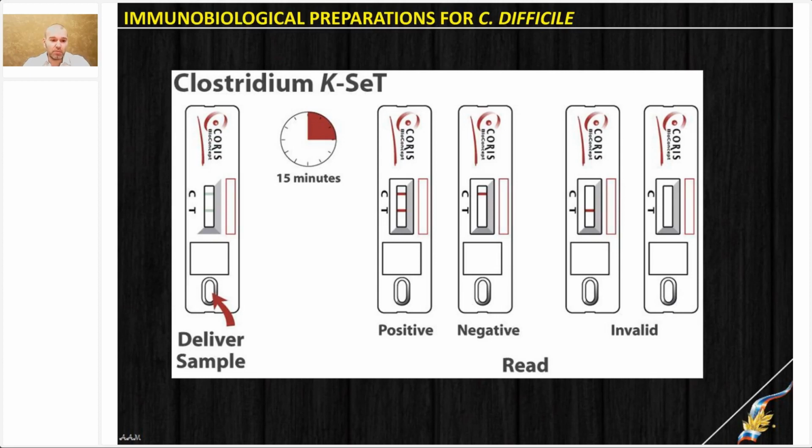It is a unique membrane which can pass only known size of complexes, and actually the same similar principle. You need to take a sample from the subject. You don't need any pure culture. The test can be done near the bed of the subject and requires about 15 to 30 minutes.